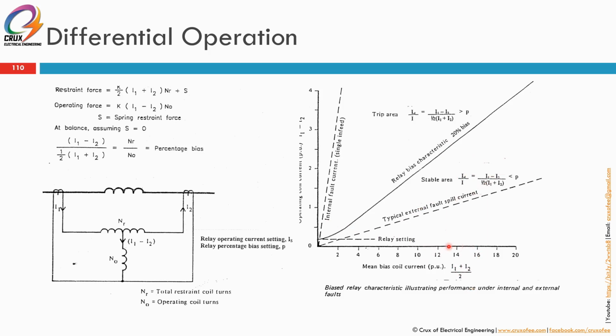Walaupun your differential is high, maksud katalah you measure the differential at this point. But because the ID is much lower than that, the point is somewhere in here lah, below the operating region, the stable region. So katalah ada internal fault here. So your bias obviously will be higher than 20% when you calculate I1 minus I2 divided by half of I1 plus I2. I1 minus I2 is your differential current divided by your restraint current. So if it's more than 20%, it will be in this region lah. And the IDIF setting is here lah, from here up to here. So this is your IDIF punya setting. Okay.